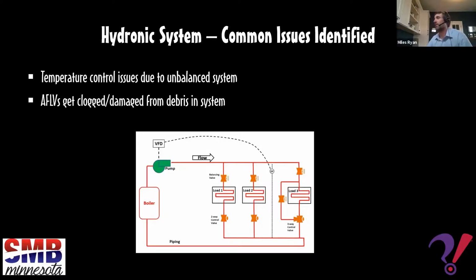Now we're back in the building because 3 years later they had installed auto flow limiting valves, which is essentially, Mark talked about this, a kind of balancing valve that basically, if there's adequate pressure in the system, it's going to internally modulate itself to limit the amount of flow that could ever go through a coil, so you're not stealing flow from your neighbors.